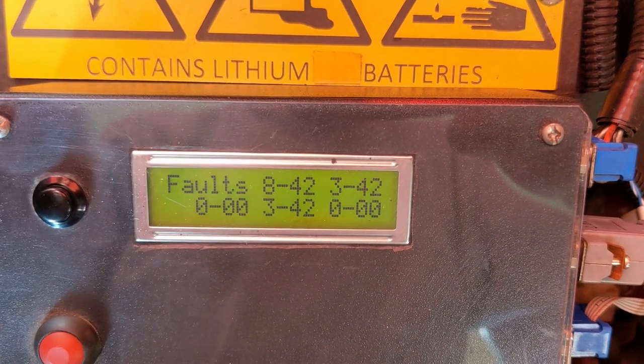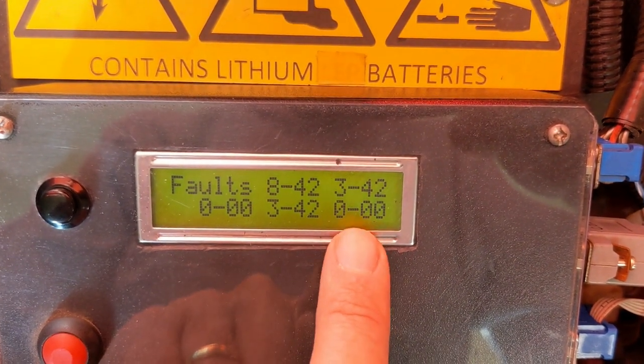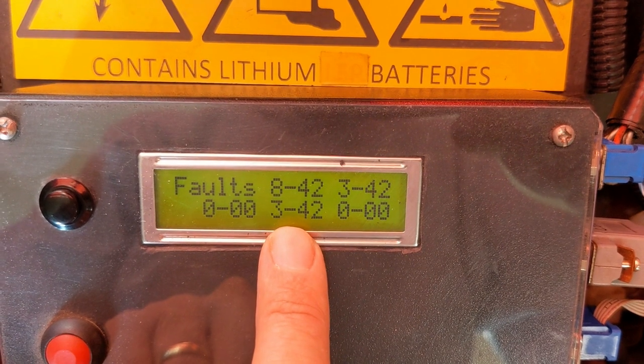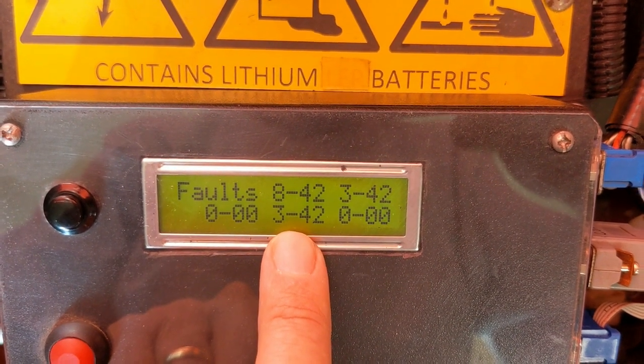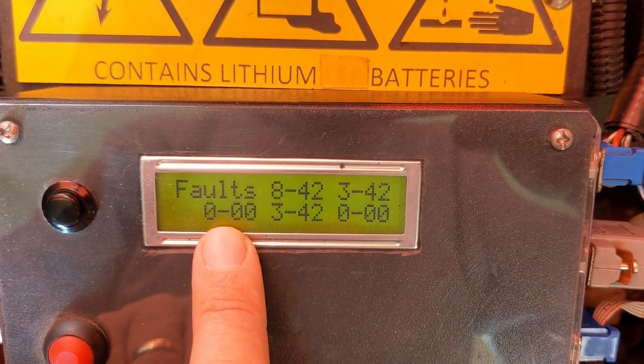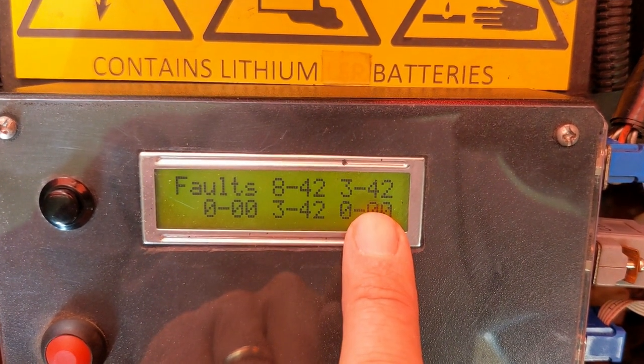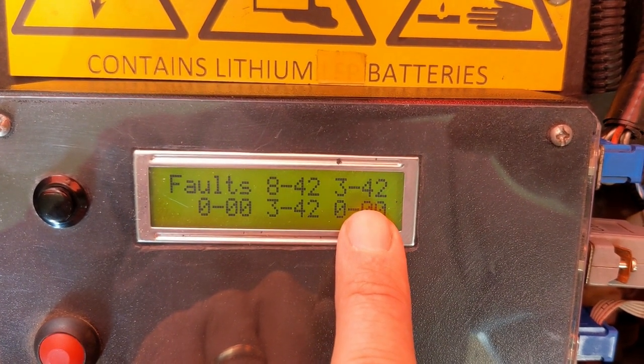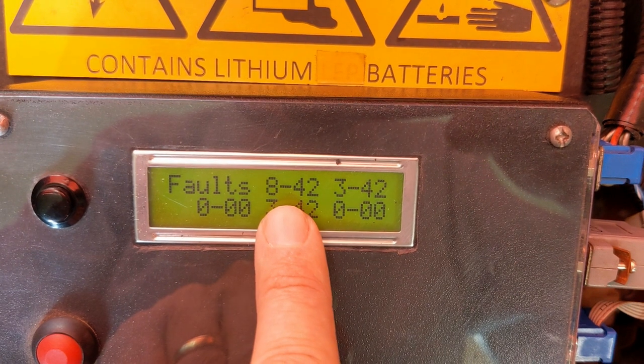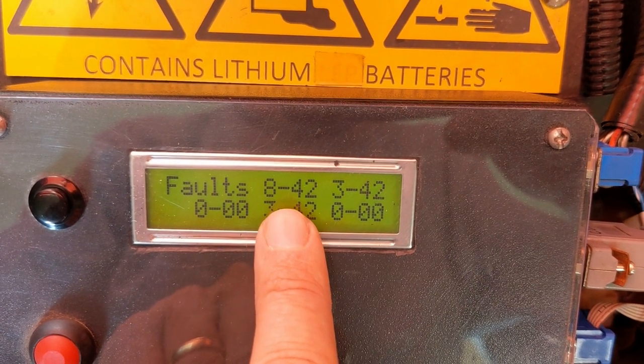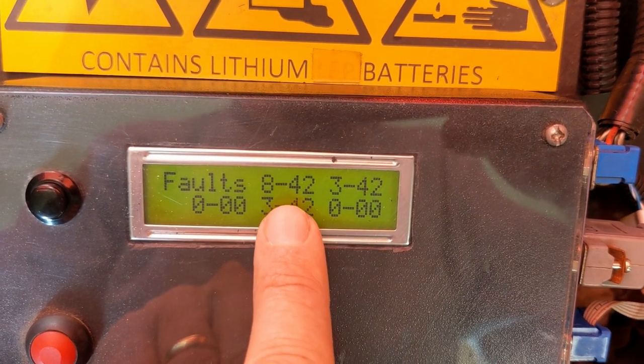If you have a look at the fault codes, these are in order. There was 0, then fault 3 for cell 42, a low cell voltage. Then I reset it, it went back to 0, and then it came up again. So again fault 3 for cell 42, and then fault 8 for cell 42. 8 is very low voltage, panicky low voltage.